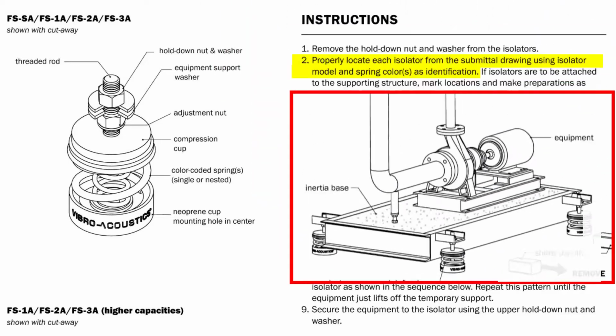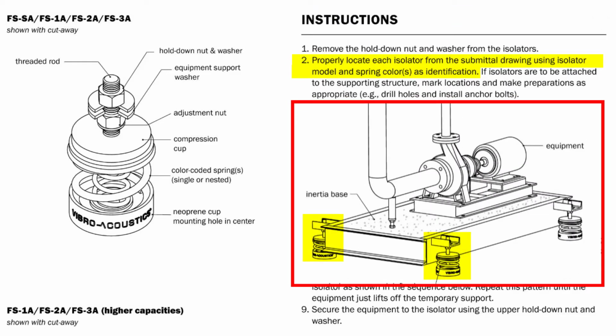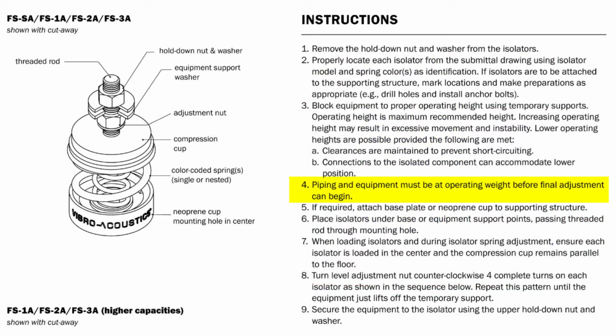In many cases with end suction pumps, the isolators on the pump end have a higher capacity than the isolators on the motor end, since they are selected to support the additional weight of the suction and discharge water-filled piping. We'll see that with the other pumps on this job. Note that the pipe and equipment must be at operating weight before final adjustment.